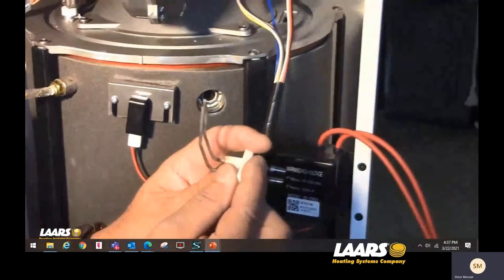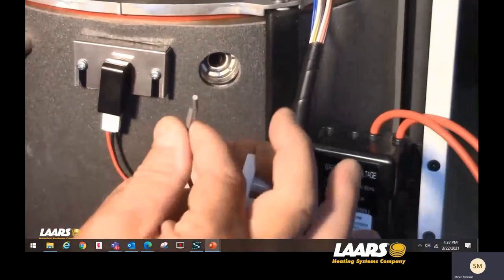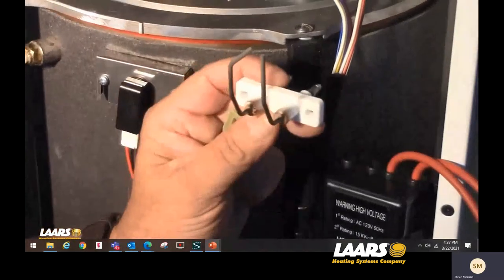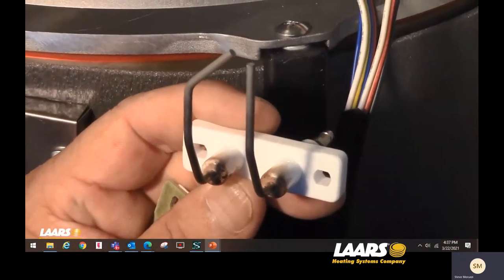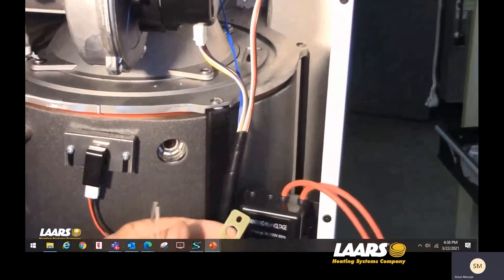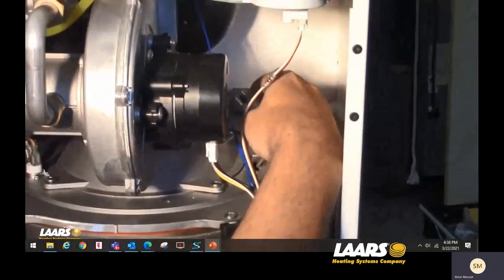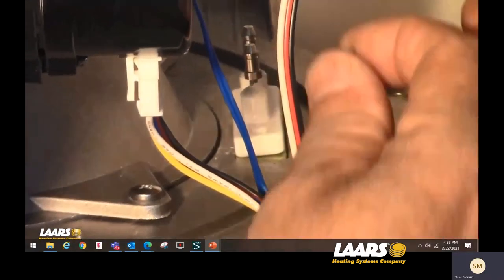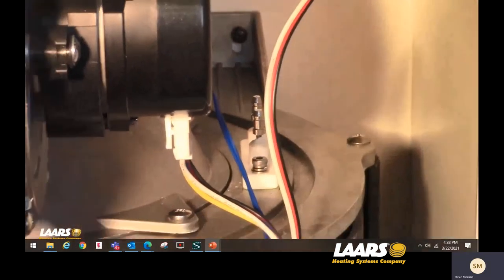Check for any corrosion or buildup of debris on the igniter. Here you're seeing a little discoloration — what you would do is take a non-abrasive cloth, a dollar bill works fine, and clean the two electrodes. Take a look at the gap of the igniter: it's 3 to 4 millimeters, which equates to one-eighth to one-quarter of an inch gap from electrode to electrode. When you're ready to reinstall, put the gasket back on, start in on that angle and come all the way down, then put your screws back in and tighten carefully. The igniter has a ceramic base, so do not over-tighten — just make it snug.